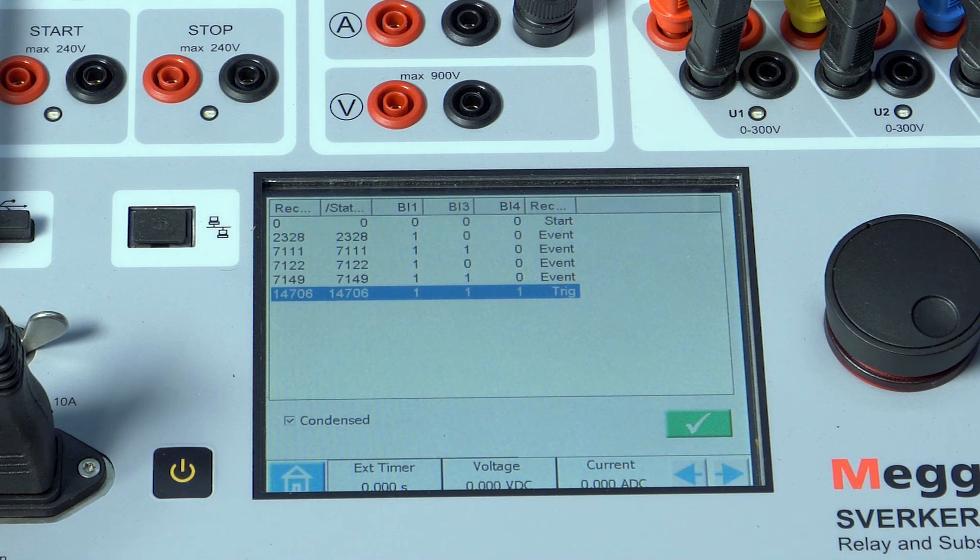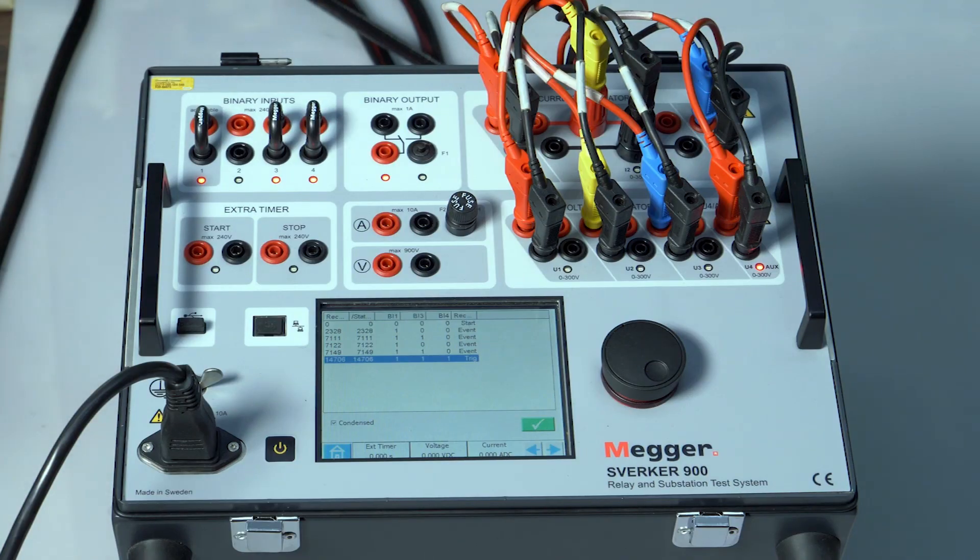In this manner, several combinations can be created based on the application. An application such as auto recloser feedback based on all pole open condition can be simulated. In this application, the R phase, the Y phase, and B phase are connected to binary input 1, binary input 2, and binary input 3 respectively.